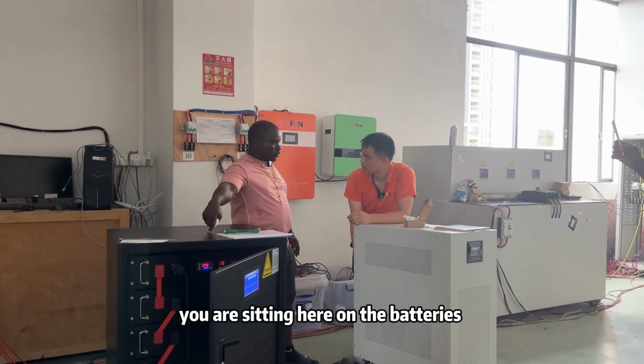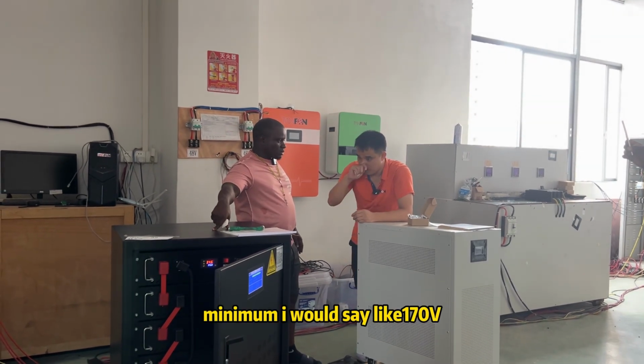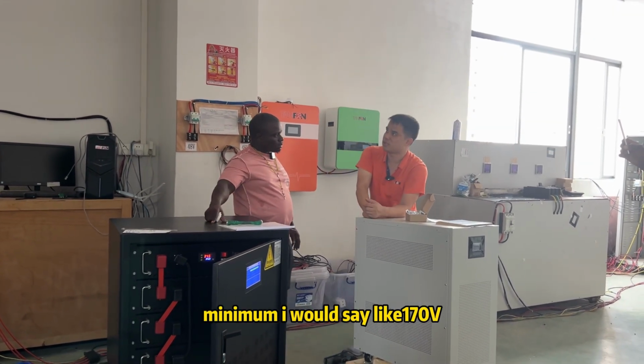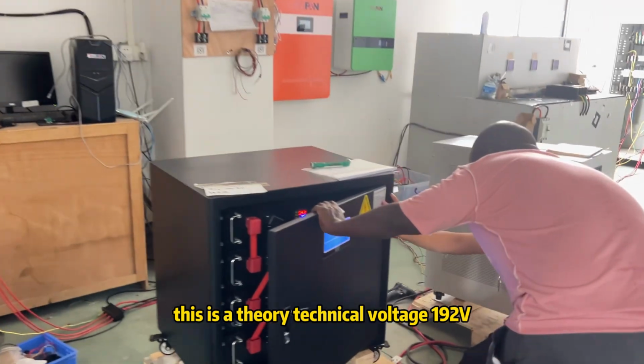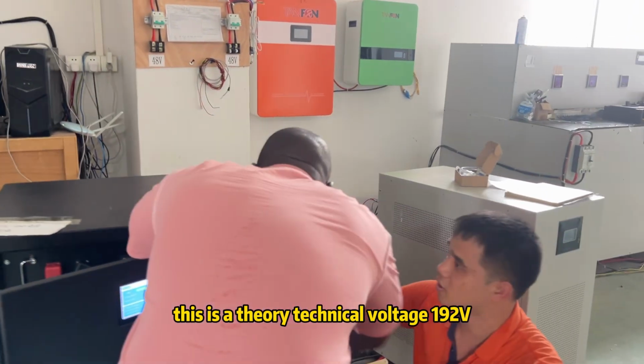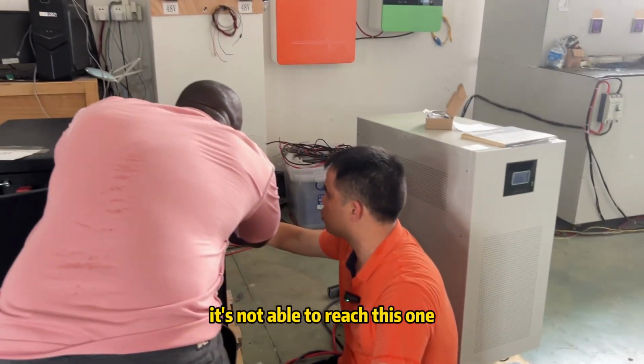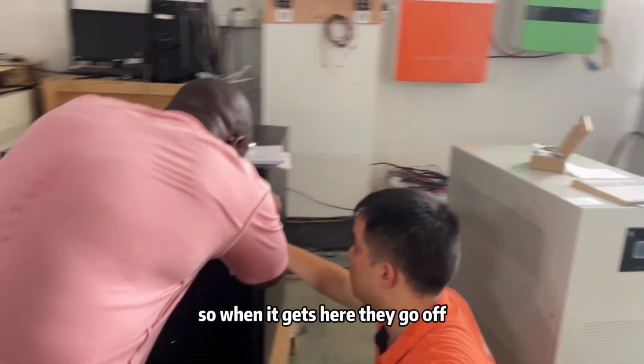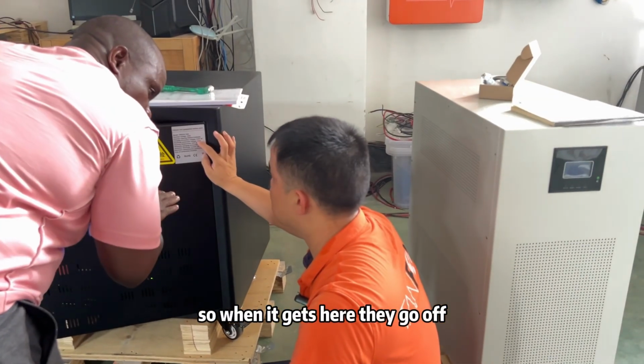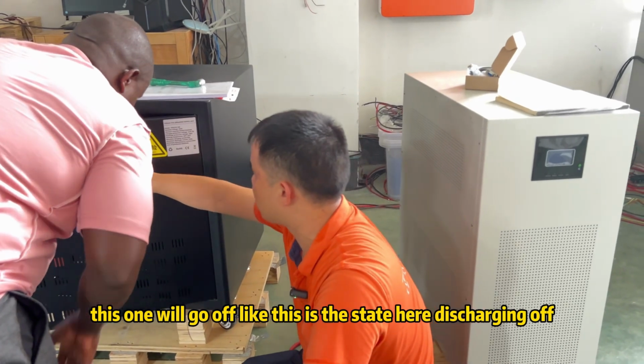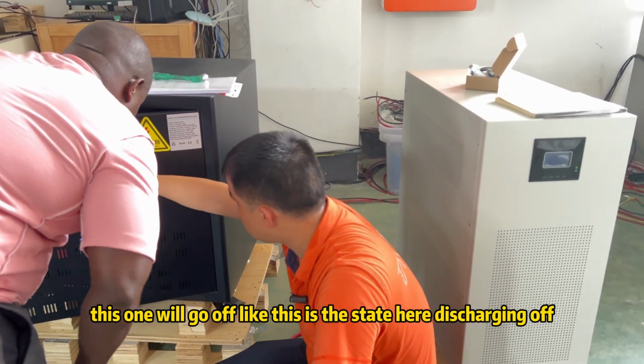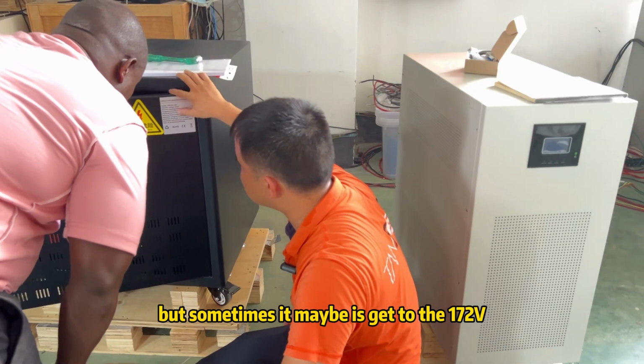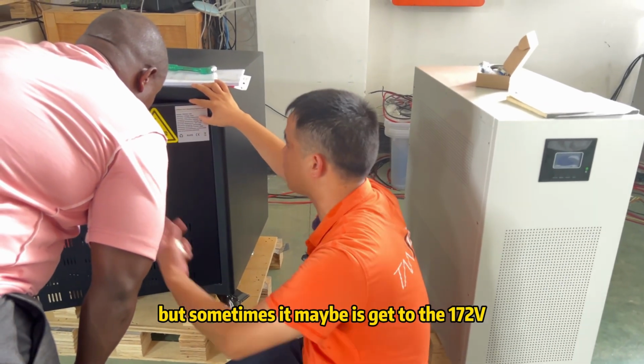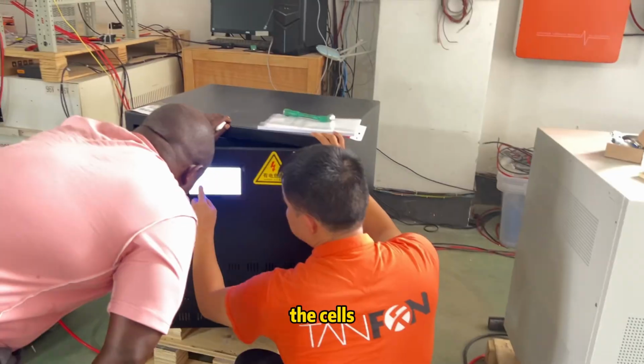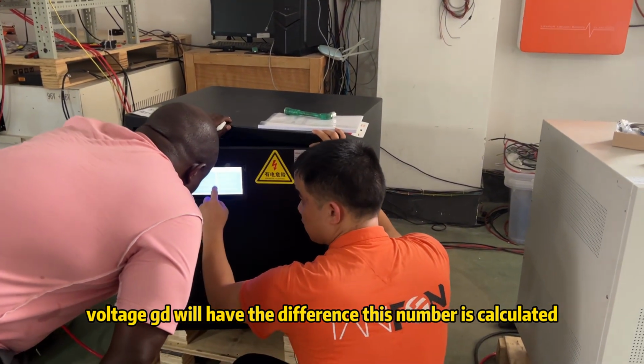What is the minimum voltage you are setting here on the batteries? Minimum, I would say like 170. The technical voltage is 192, but it's not able to reach that. So when it gets here, they go off — this state is discharging off. But sometimes when it gets to 170, it will stop to check discharge, because the cells' voltage will have a difference.